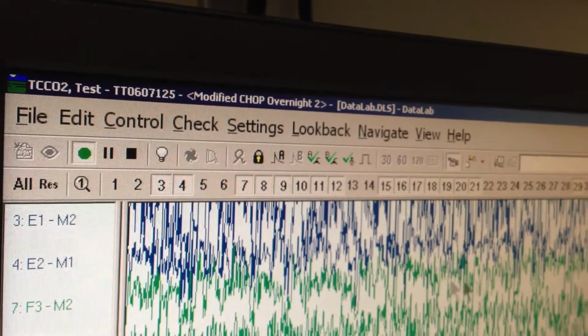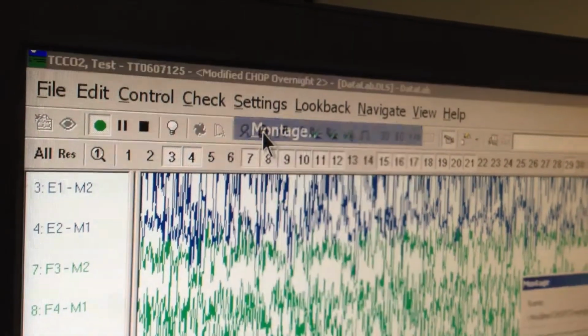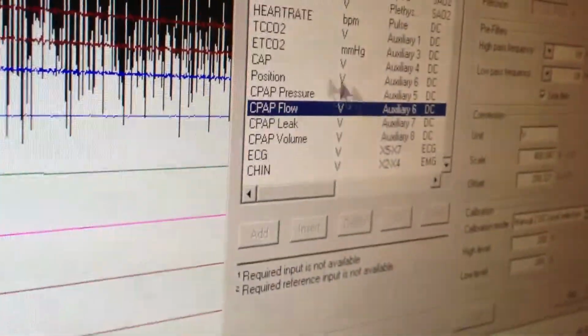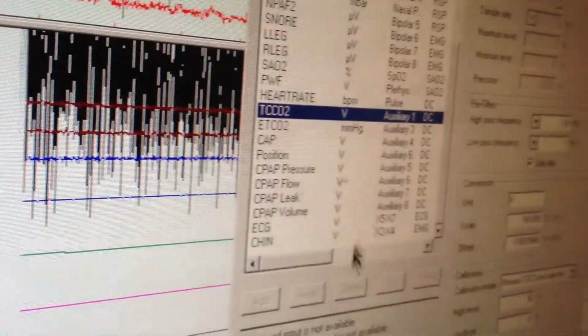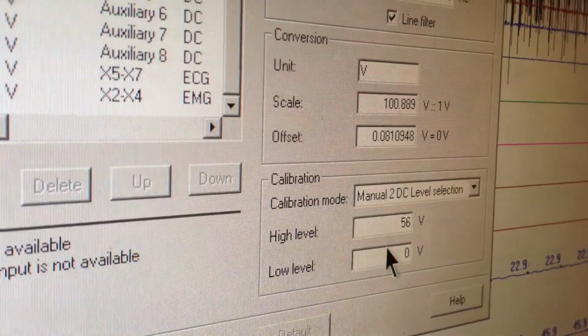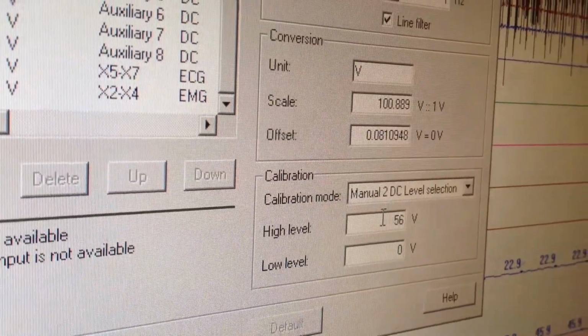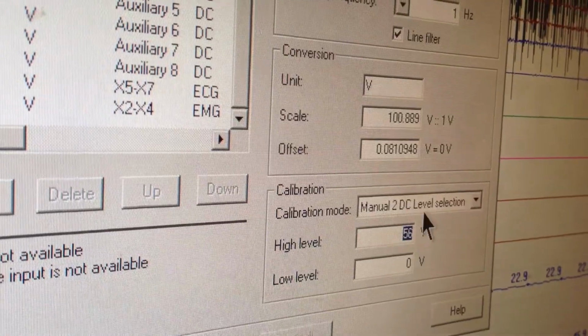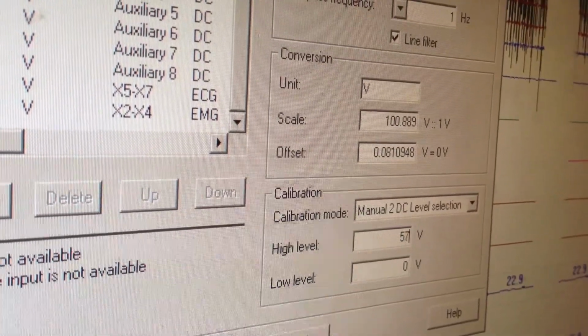from the TCOM to the computer. So you want to come to the computer and go into settings, montage, scroll down to the CO2, and come over to calibration to the high level, and you want to make sure the high level equals what was on the TCOM screen. On the TCOM screen it was reading 57, so we want to change this value to equal 57 as well. Then you want to come out, close, and start the calibration for the TCOM.